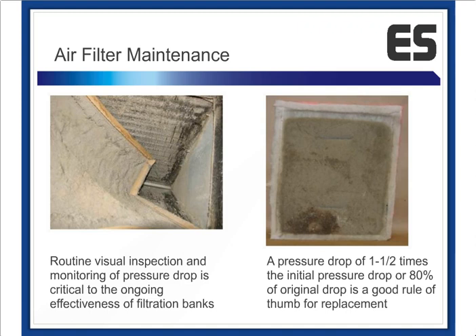That's pretty good filtration, and is going to keep a lot of contaminants from the outside from coming into the building. But like anything else, it's something that needs to be managed over time. A couple of examples here are just where filters can fail, and if we don't catch those, then all of those systems that we've designed to put in place won't work correctly. As filters in a system start to get built up with debris, dust, pollen, and particulates, then we start to see a pressure difference across that filter. And facility managers will monitor that pressure drop to give them an idea of when they should be changing the filters.